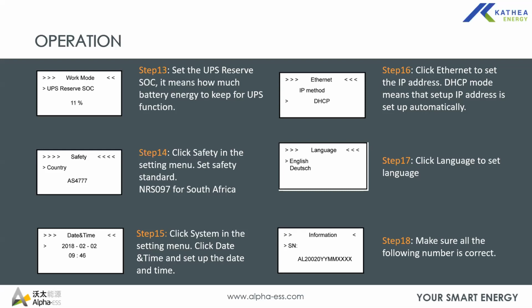And then out of safety, there is system. On system, basically you set basic parameters: your date, your time, and then there are Ethernet settings. On Ethernet settings, you can set the system to DHCP, which means the system automatically picks up the IP address of the internet connection. However, we don't recommend static, but if there is need to, you can change the IP mode to static. Then you would need to manually set the IP address, the subnet mask, and the gateway for the internet that you're connecting to the system, such that the system can access the Alpha server for remote monitoring and control.